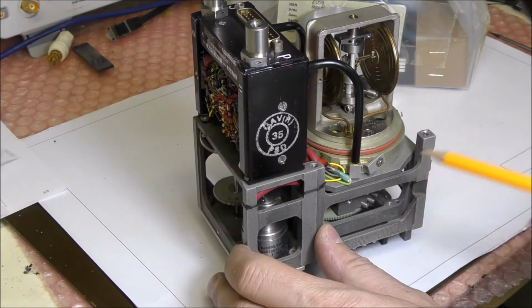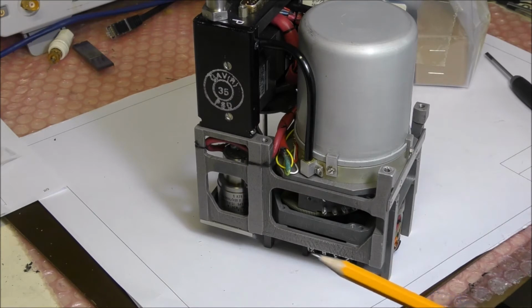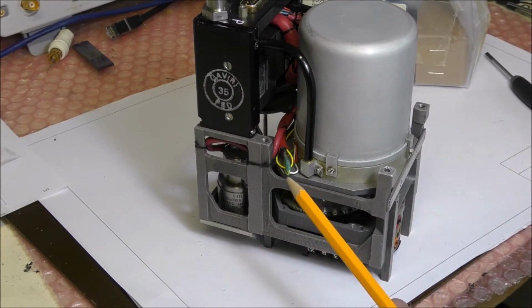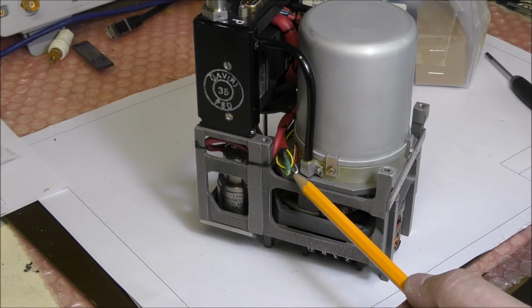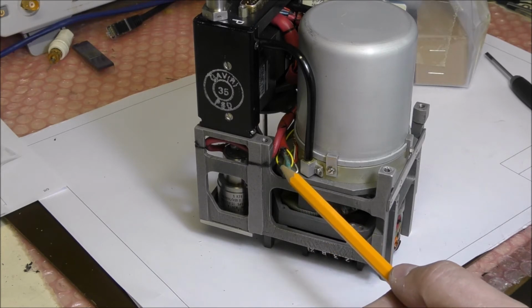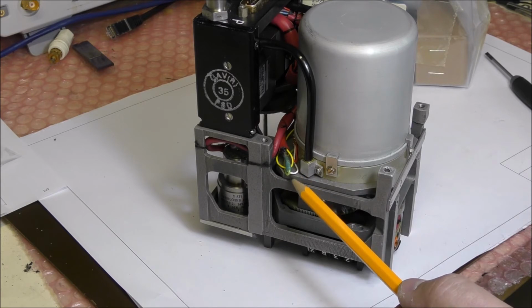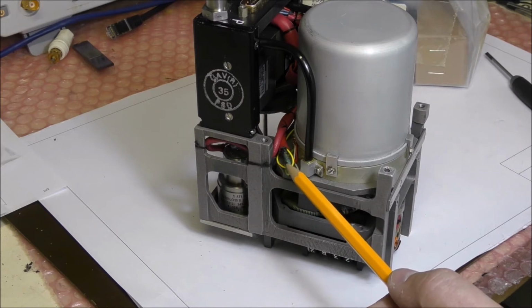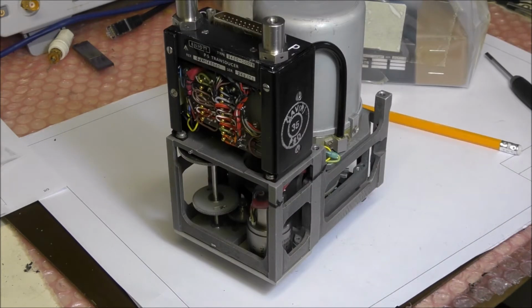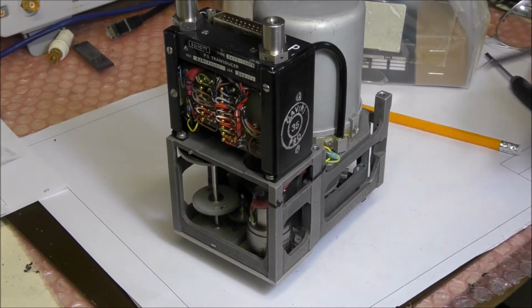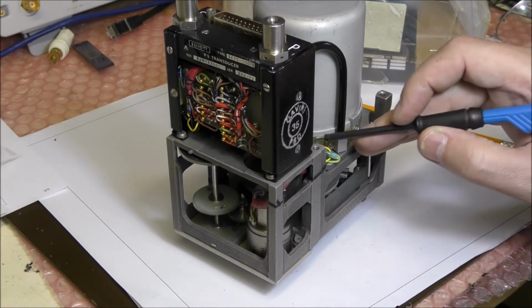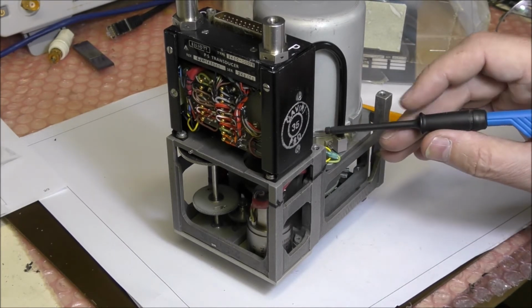from these wires here. We can see that the connection between the electronics and the LVDT sensor uses 4 terminals. 2 wires are shielded and 2 others are not. So obviously the 2 shielded cables are connected to the measurement coils and the 2 others are the excitation signals. So I will try to find the corresponding pins with these measurement signals. So there is a white wire and a green one.